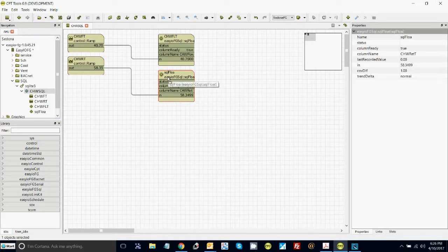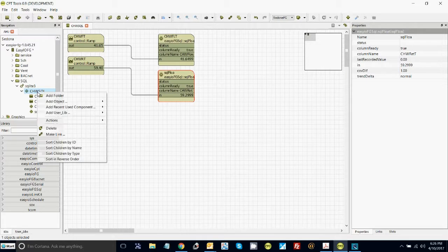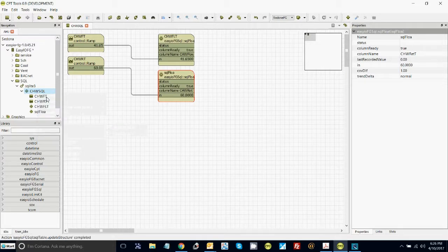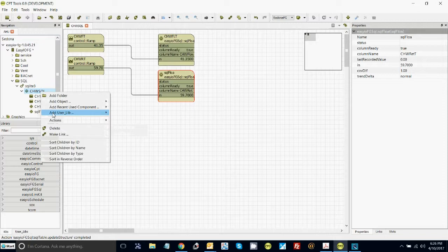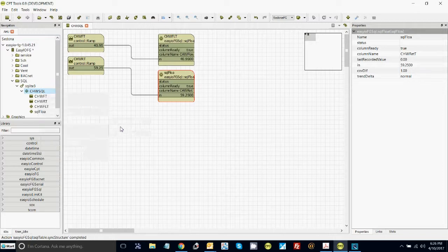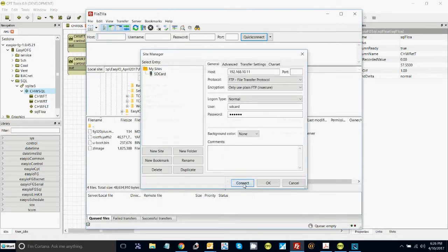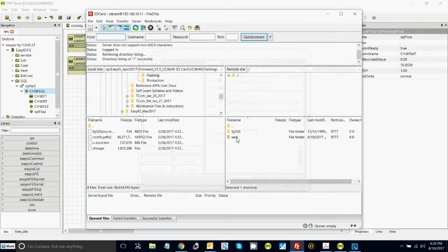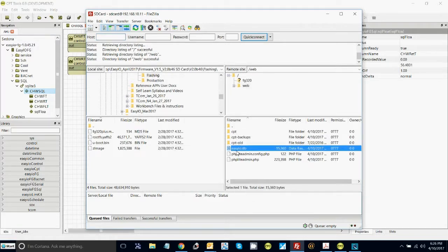Now what we need to do to create the database is move your mouse across to the table name, do a right click, and do action update structure and sync structure. That has now created your database. To prove it let's open FileZilla and go have a look at the SD card because that's where this file will live. Log in — the right hand side is the SD card. Go into web. There's the file we've just created: easyio.db.